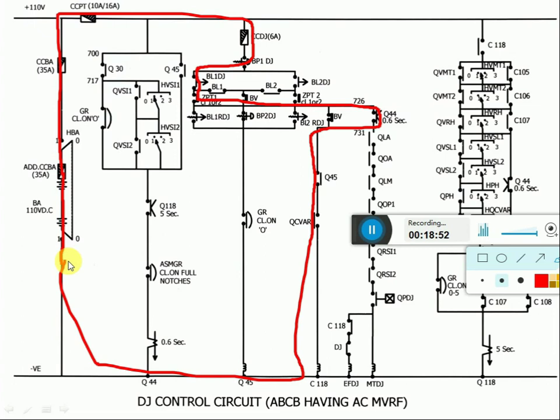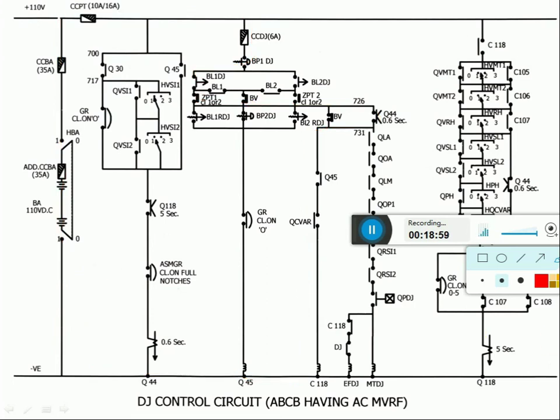How does the C118 coil get energized? We have seen now. If the C118 coil is not picking up, not closing, ensure that no cable at C118 is disconnected. If disconnected, try to connect. Operate C118 2 or 3 times with precautions to check the flexibility of C118.